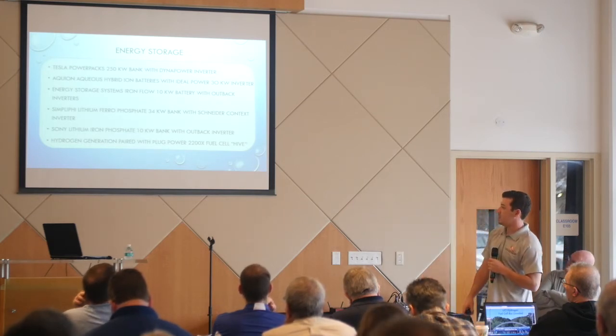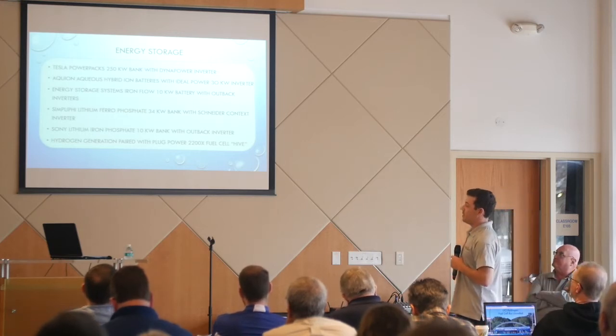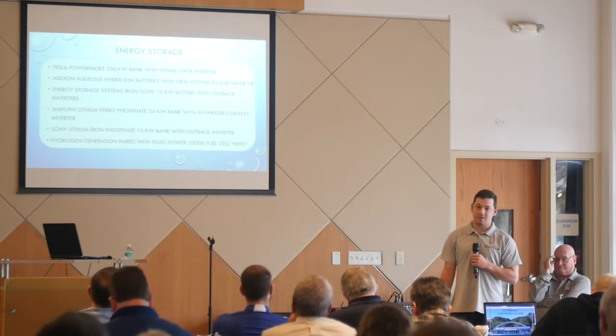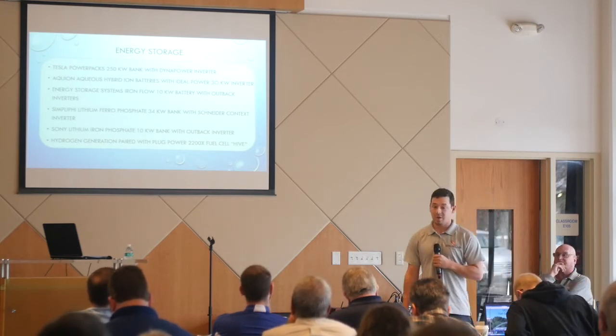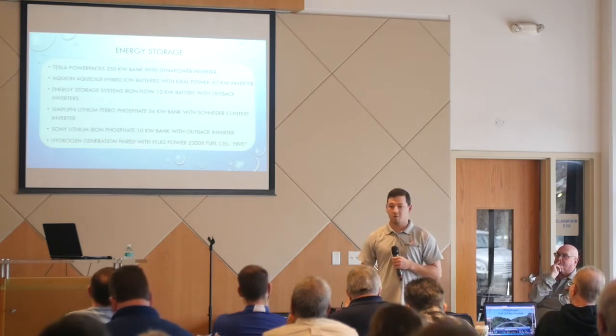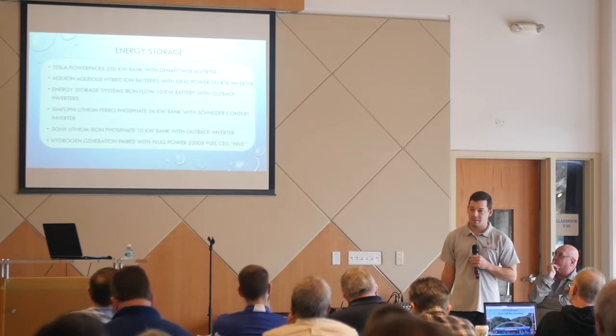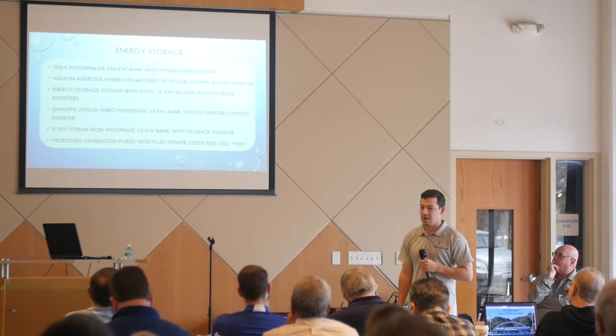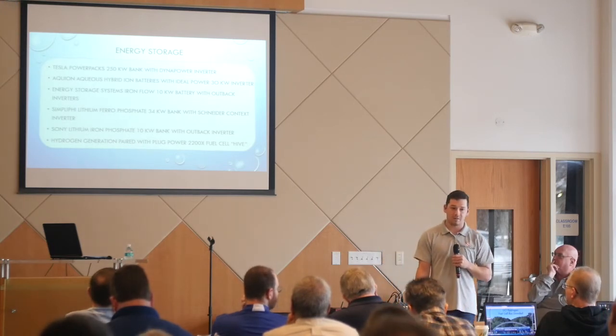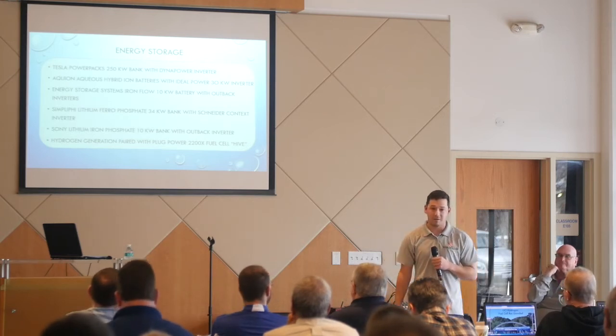So our second largest would be our Aquion batteries. Those are palletized aqueous hybrid ion batteries, so they're basically saltwater batteries. They're huge. They're about 4,500 pounds each, and each one of them is 48 volts. So they're deep cycle batteries, a totally different application than the Tesla, which is lithium ion cobalt, which is really strong punch, hits you hard, just like that's why it's so perfect for cars. You wouldn't want to put an Aquion battery in your car, ever.